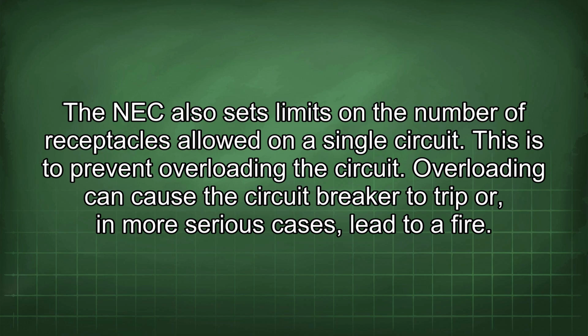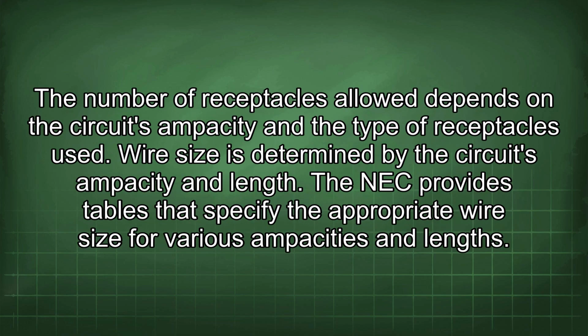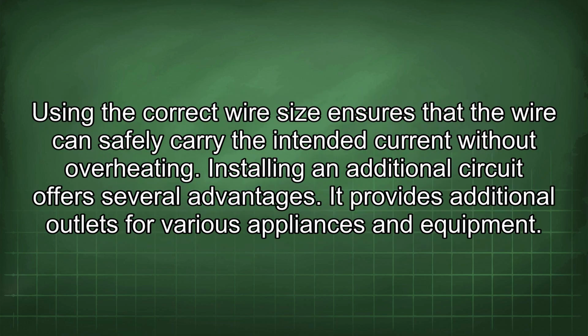The NEC also sets limits on the number of receptacles allowed on a single circuit. This is to prevent overloading the circuit. Overloading can cause the circuit breaker to trip or, in more serious cases, lead to a fire. The number of receptacles allowed depends on the circuit's ampacity and the type of receptacles used. Wire size is determined by the circuit ampacity and length. The NEC provides tables that specify the appropriate wire size for various ampacities and lengths. Using the correct wire size ensures that the wire can safely carry the intended current without overheating.